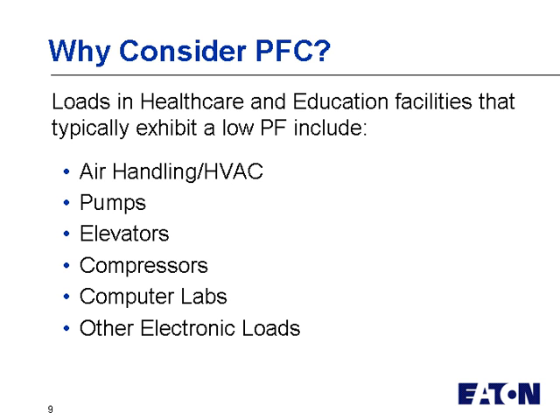Now, we're here to discuss healthcare and education facilities, and so we wanted to point out a couple loads that might be important in these facilities that exhibit low power factor. Specifically, if you can think of any motors in your facility, those motors will typically have a little bit lower power factor. Things like HVAC, pumps, elevators, compressors. And then there's other things like electronic loads like computers and other UPSs and things like that often exhibit a low power factor, especially when they have a lot of harmonic current.